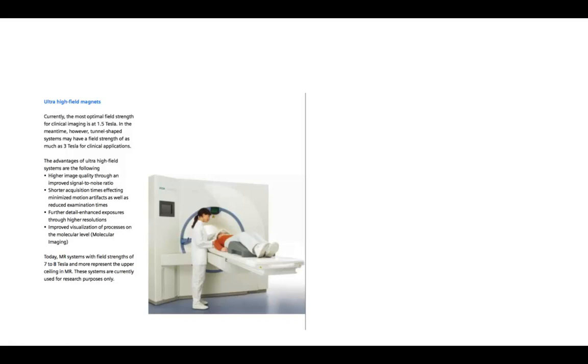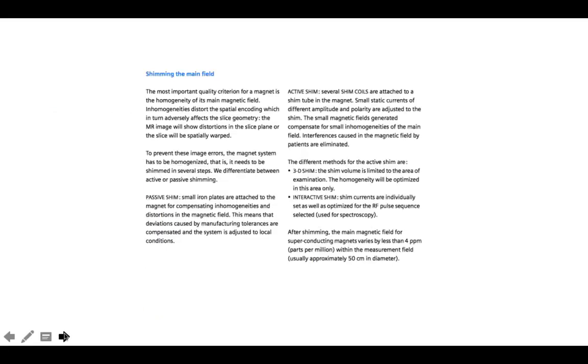level. So there are some systems available today that do reach the 7 to 8 Tesla level. Most of these represent the upper ceiling in MR, and they're currently used for research purposes only. There are a limited number of studies that have used this level of field strength with humans. However, it's primarily reserved for animal studies until the safety can be ascertained.